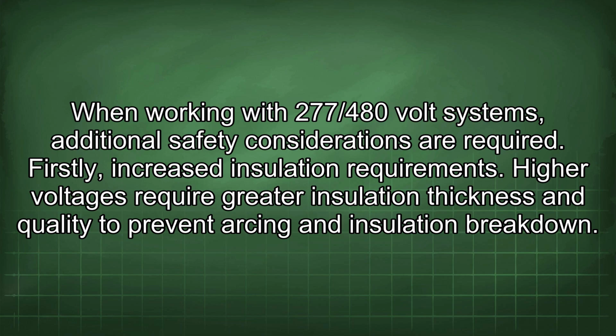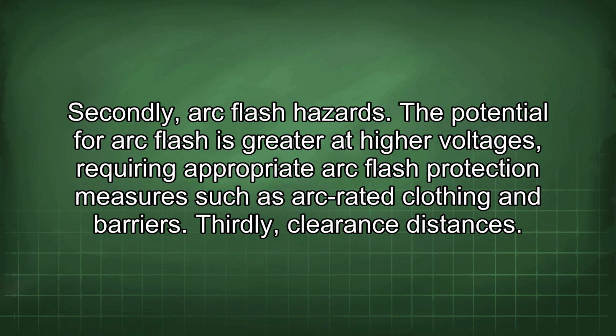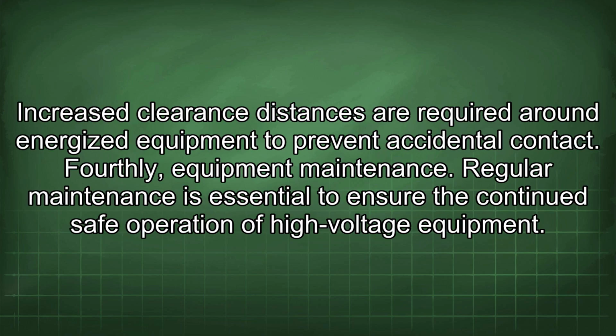Firstly, increased insulation requirements. Higher voltages require greater insulation thickness and quality to prevent arcing and insulation breakdown. Secondly, arc flash hazards. The potential for arc flash is greater at higher voltages, requiring appropriate arc flash protection measures such as arc-rated clothing and barriers. Thirdly, clearance distances. Increased clearance distances are required around energized equipment to prevent accidental contact. Fourthly, equipment maintenance. Regular maintenance is essential to ensure the continued safe operation of high-voltage equipment.